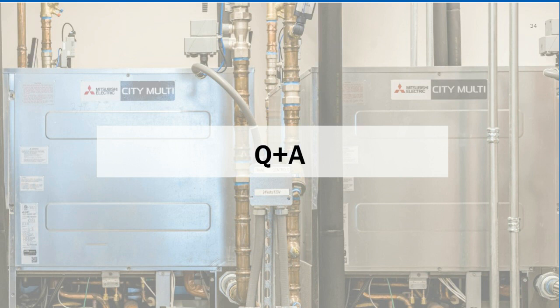Most stuff we do in the South Texas area tends to be air source. You really have to look at the ground conditions to see if water source makes sense in your location. Most of the stuff around here in San Antonio, it doesn't make sense to do the full system on it. The water source or geothermal part of this one is just kind of knocking the peaks off. It's not handling the whole load of the building, except in some of the shoulder seasons, where it can. But most of our systems here in San Antonio, or really Austin and South Texas, are mostly air source.